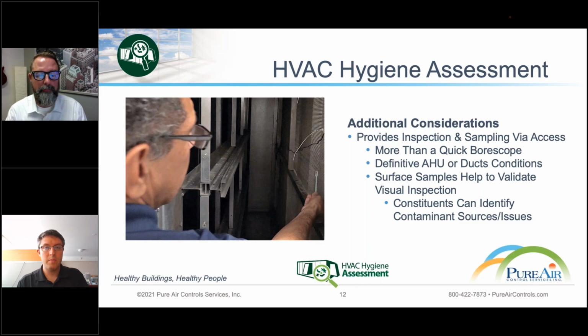So we do a lot of these inspections, and it entails more than just using a borescope and poking around to look at a diffuser, supply, or return register. We're actually getting into the ductwork, accessing it, visually inspecting it with our eyes, lights, and cameras, not just poking around with a little borescope. Those are helpful, but it's foundational to take an actual look, especially with terminal units like VAVs and reheat coils. They play such a substantial role and get so overlooked. So it's a matter of getting in and gathering more detail.